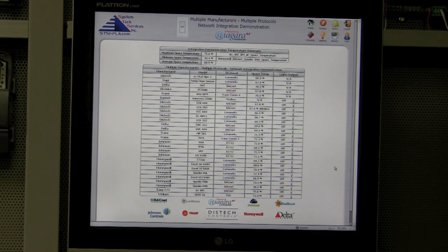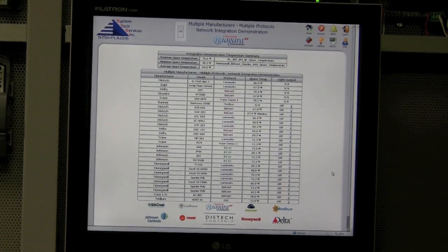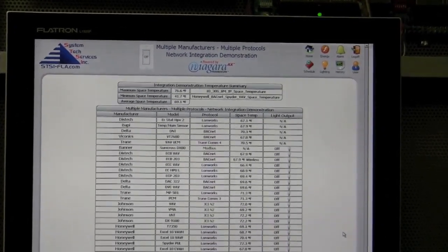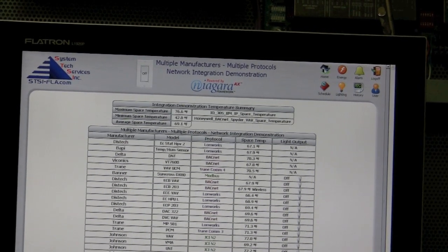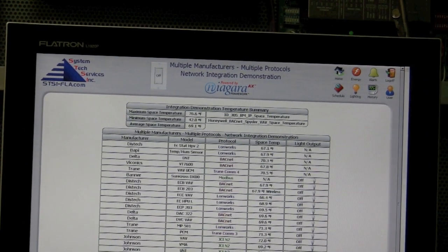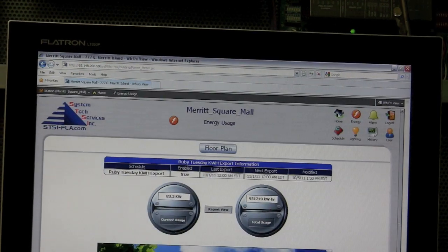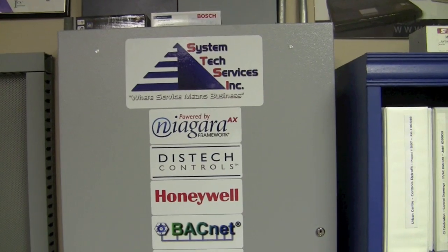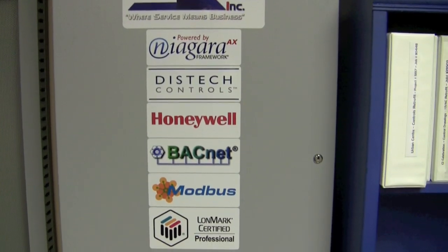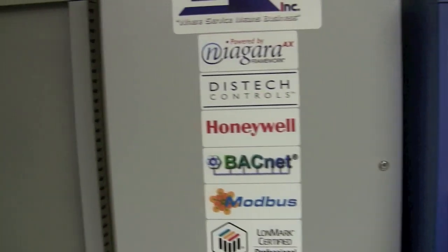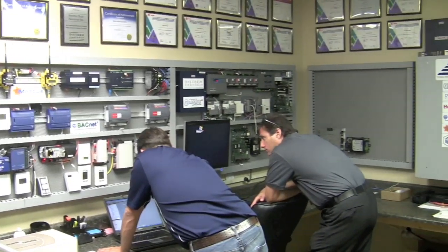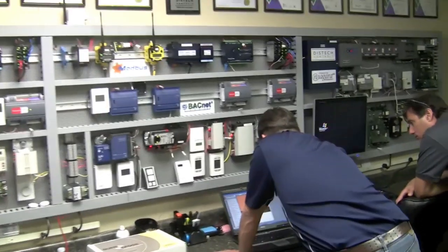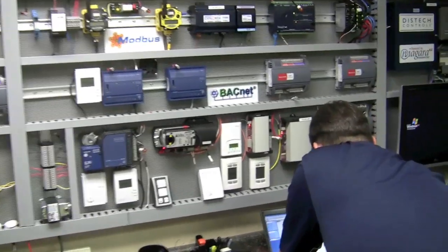If all your errors are less than half a degree, you don't need to go any farther. If you've got an error that's 5 degrees, you go right to that system. This is a value add that System Tech Services adds for customers. So monthly or real-time — if something goes out of deviation, you're immediately alerting them. That eliminates a lot of cost. Another contractor without this system has to go unit to unit and probably won't even know unless he checks. To check something like a mall would be cost-prohibitive. Building this into the system is huge for an owner — it's part of our base, what we put in every system. Without it, you just wait on people to complain.